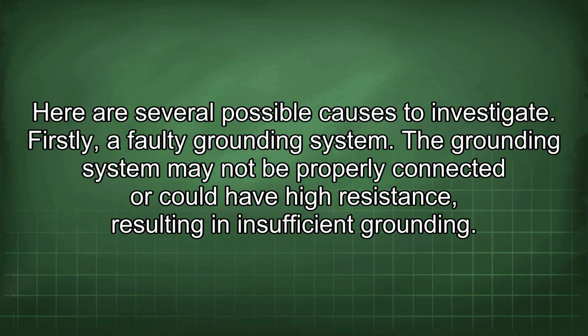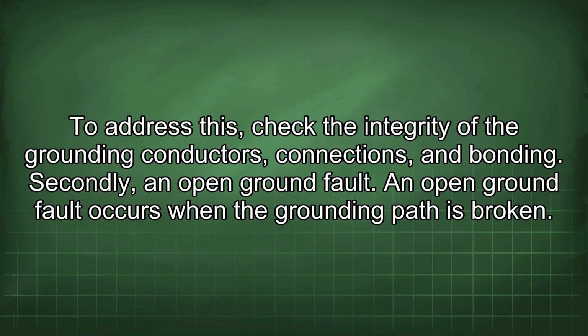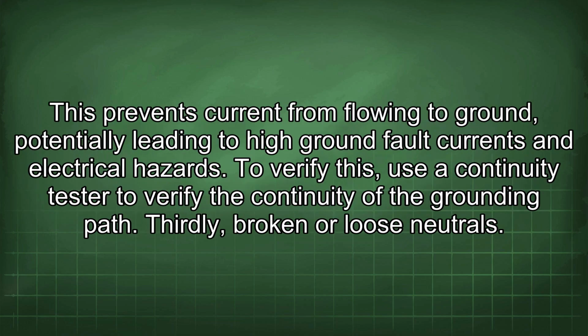Firstly, a faulty grounding system. The grounding system may not be properly connected or could have high resistance, resulting in insufficient grounding. To address this, check the integrity of the grounding conductors, connections, and bonding. Secondly, an open ground fault. An open ground fault occurs when the grounding path is broken. This prevents current from flowing to ground, potentially leading to high ground fault currents and electrical hazards. To verify this, use a continuity tester to verify the continuity of the grounding path.